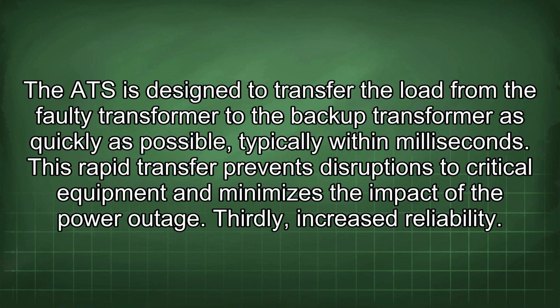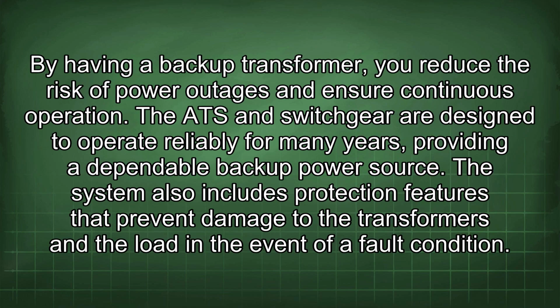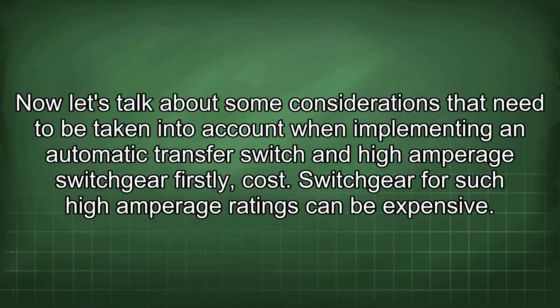Thirdly, increased reliability. By having a backup transformer, you reduce the risk of power outages and ensure continuous operation. The ATS and switchgear are designed to operate reliably for many years, providing a dependable backup power source. The system also includes protection features that prevent damage to the transformers and the load in the event of a fault condition. Now let's talk about some considerations that need to be taken into account when implementing an automatic transfer switch and high amperage switchgear.